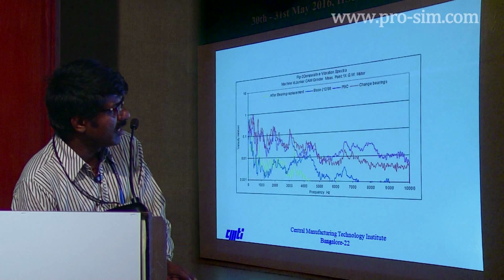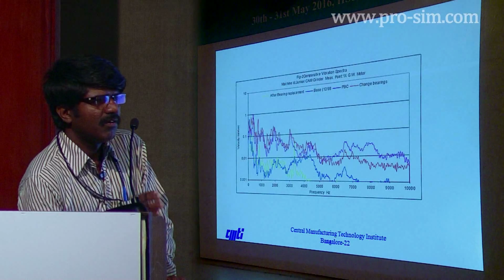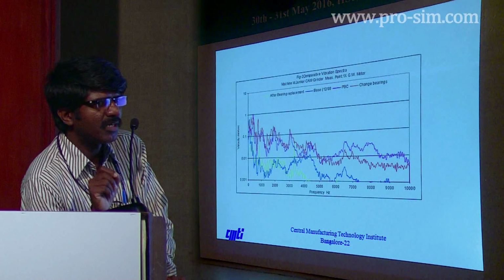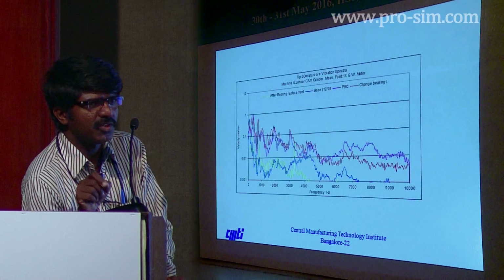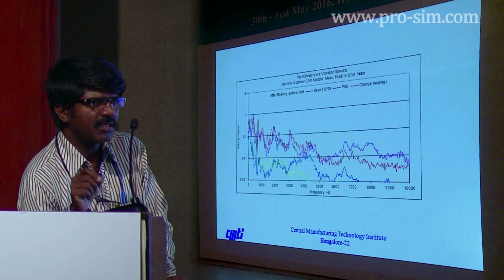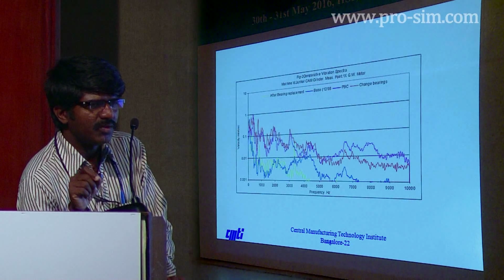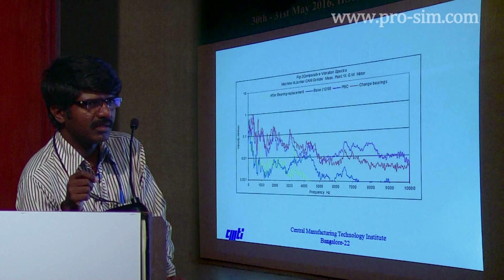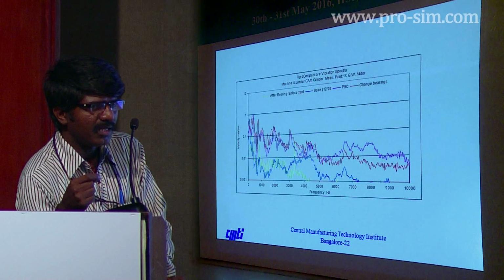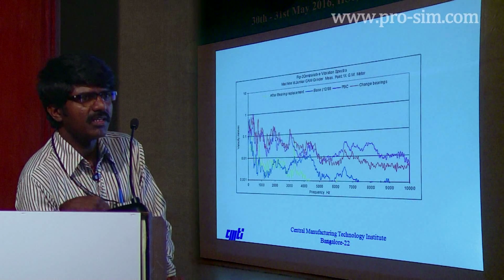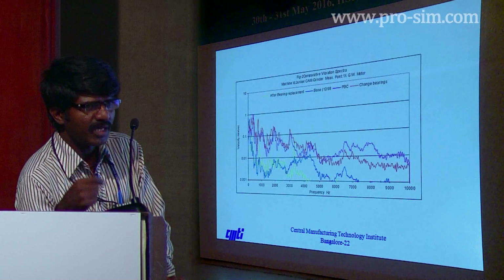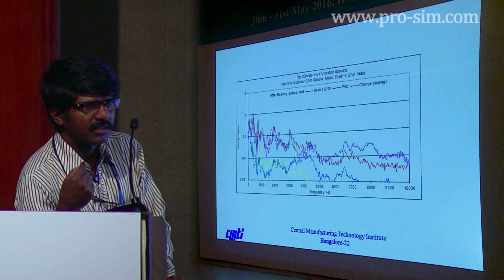The blue color indicates the base signature. For condition monitoring of machines, the most important thing is the base signature. When the machine is new, please collect the base signature and preserve it. It is very useful for future comparison. Suppose once you replace the bearing, that signature will go off and a new signature will come, because each bearing will have different signatures. Okay.